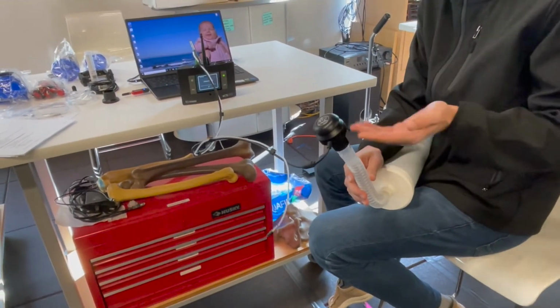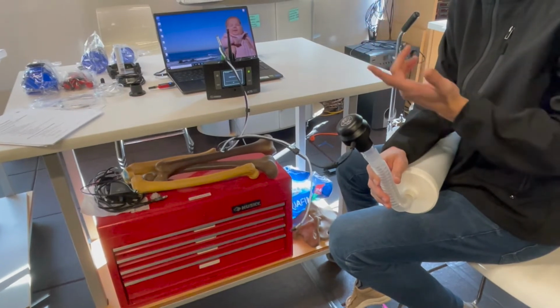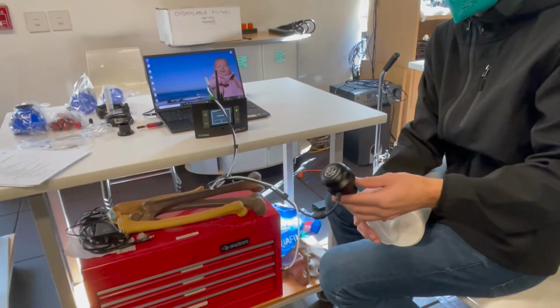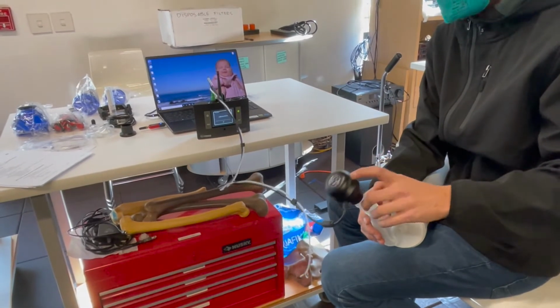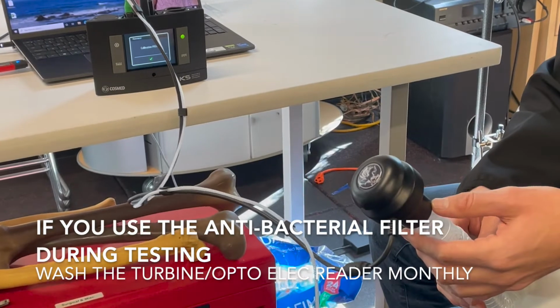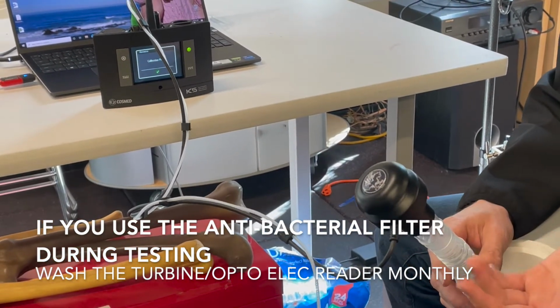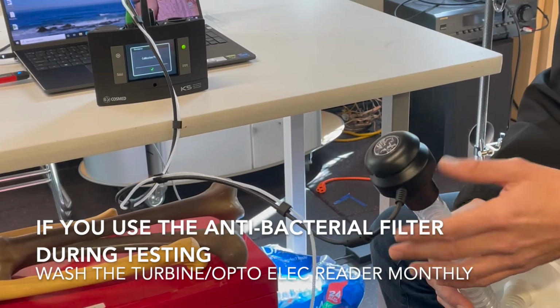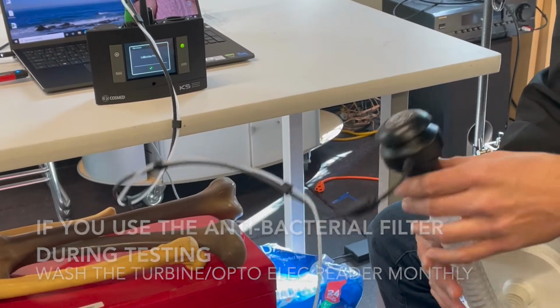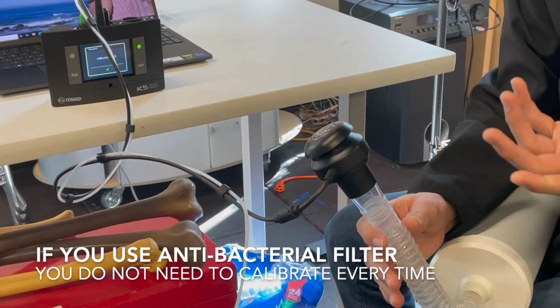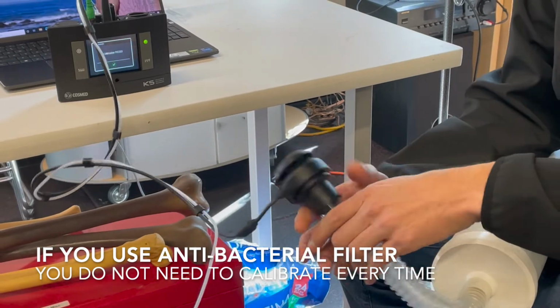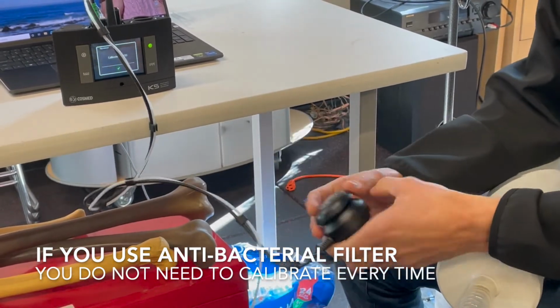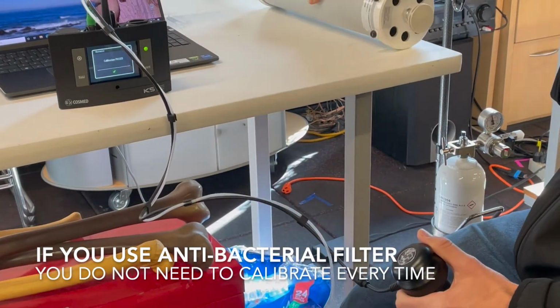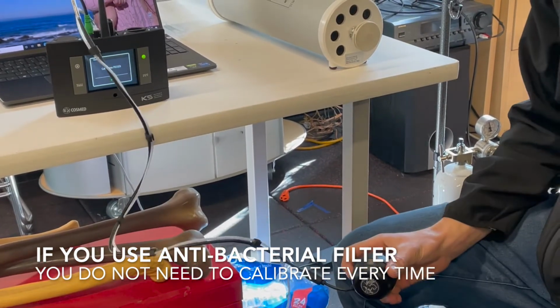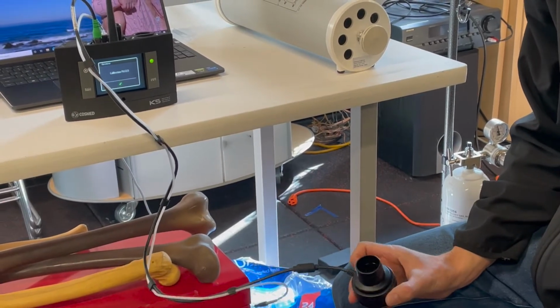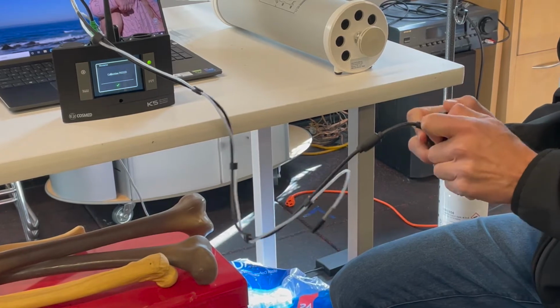Which is another thing that's super nice about this, because you have the AB/AV adapters to use antibacterial filters while exercise testing. Since you're not washing these between tests, it only needs to be washed every month. That means you don't really need to calibrate between each test, because you're not washing it and potentially introducing something that could damage it. That's because they are super linear. Sorry to interrupt, but if we start using the filters on the cart, that's the same, then we wouldn't have to calibrate every time? Yes, correct.